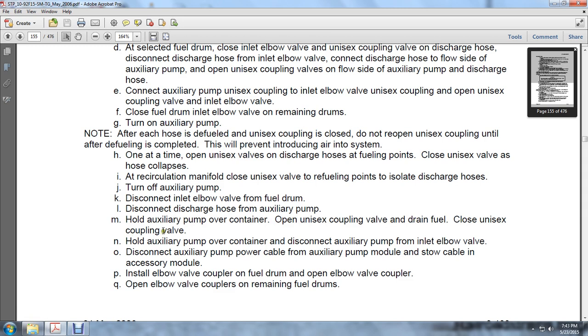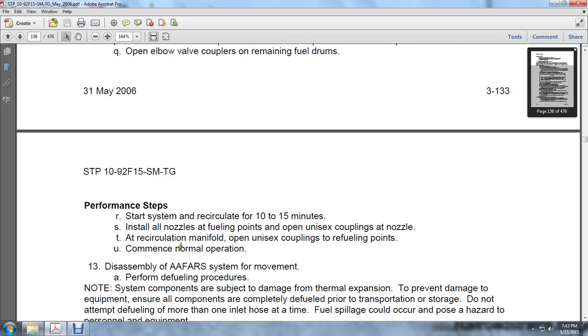Close the unisex coupling valve. Hold the auxiliary pump over the container and disconnect the auxiliary pump from the inlet elbow valve. Disconnect the power cable from the auxiliary pump and the module and stow the cable in the accessory module. Install the elbow valve coupler on the fuel drum and open the elbow valve coupler. Open the valve couplers on the remaining fuel drums.